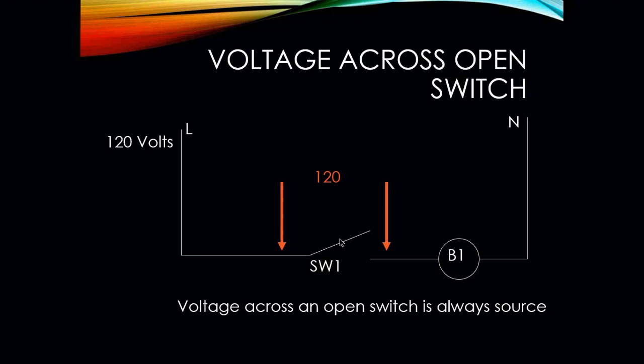So, voltage across an open switch. Remember, voltage across an open switch, you're always going to read source voltage. The reason why we are reading source voltage is because electricity is now going to take the path of least resistance. So since the switch is in the open position, it cannot go that way. It's open. So it's going to come through my meter. My meter will now pick up that difference in potential. So therefore I have 120 volts.